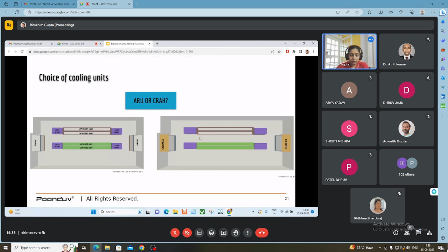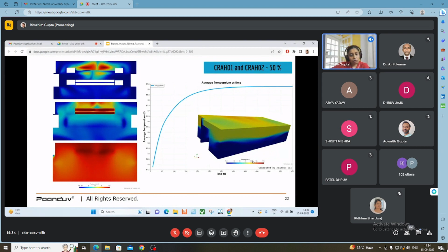We simulated CRAH units in both arrangements working at 50% capacity, and got the best result for that scenario. The average temperature is around 89.5 degrees Fahrenheit, with cold air sitting at the bottom. There's complete stratification of cold and hot air at the bottom and top, and maximum temperature is also reduced compared to the previous ARU scenario.